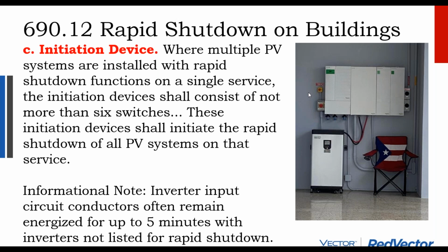And so what happens is if you don't have rapid shutdown, and you turn the inverter off, you still have voltage up on the array. And even if you turn the array off, you would still have voltage in the conductors between the array and the inverter, because electricity doesn't just magically disappear. It needs to be drained off. And so the way that rapid shutdown kind of works is they press the initiation device and the modules up on the rooftop get disconnected, and then either fans inside the inverter or other kinds of load, a little small heaters inside the rapid shutdown devices themselves, they quickly consume what remaining voltage is in the conductors between the array and the inverter and burn it off within a period of 30 seconds.